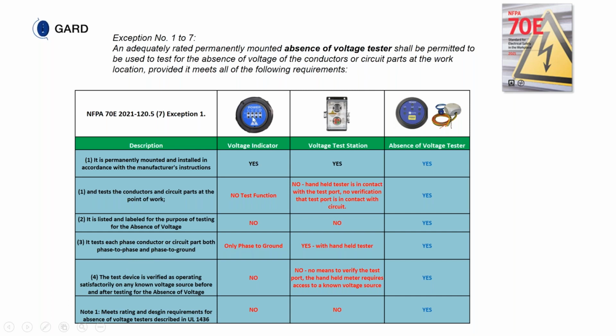Now, the one good thing about this one is it doesn't bring high voltage to the door, because this one has, what do you call it? Fiber connected to the door. So it doesn't bring voltage to the door. This one does bring voltage to the door. And you have to manually test the voltage, but then you got to go and test it to a known source. So this does not comply with NFPA 70E. The I Gard IAVT does not bring high voltage to the door or to the front of the panel. It's a very low voltage.